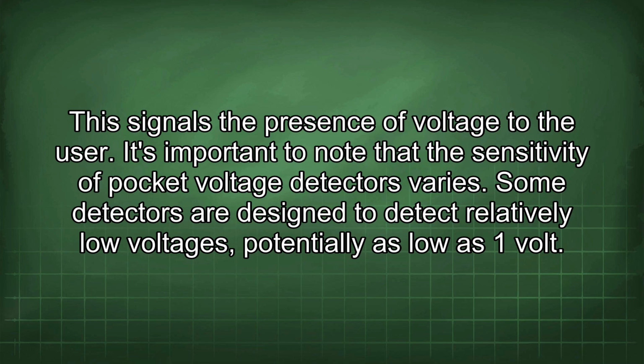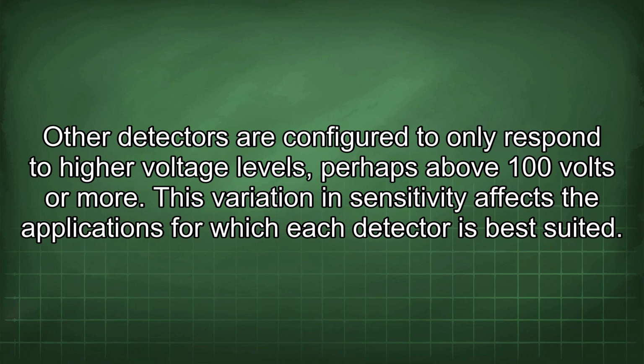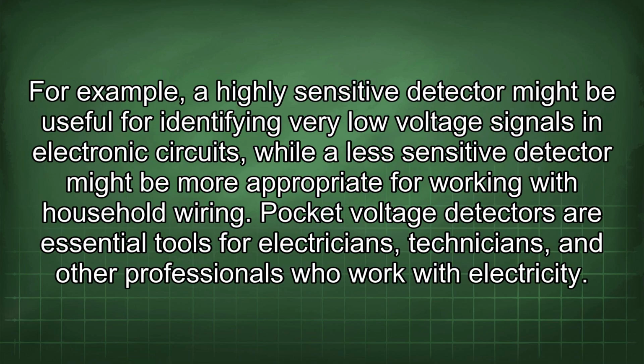It's important to note that the sensitivity of pocket voltage detectors varies. Some detectors are designed to detect relatively low voltages, potentially as low as 1 volt. Other detectors are configured to only respond to higher voltage levels, perhaps above 100 volts or more. This variation in sensitivity affects the applications for which each detector is best suited. For example, a highly sensitive detector might be useful for identifying very low voltage signals in electronic circuits, while a less sensitive detector might be more appropriate for working with household wiring.